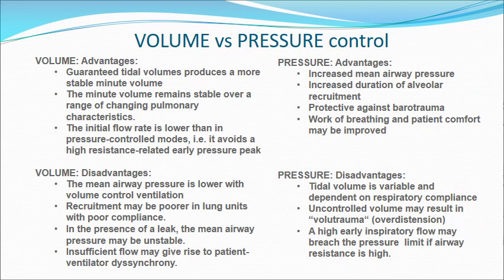So let's discuss the advantages and disadvantages that come from the difference in those pressure, volume, and flow waveforms between volume control and pressure control. So volume control has the advantage that you get a guaranteed tidal volume, which produces a more stable minute volume.